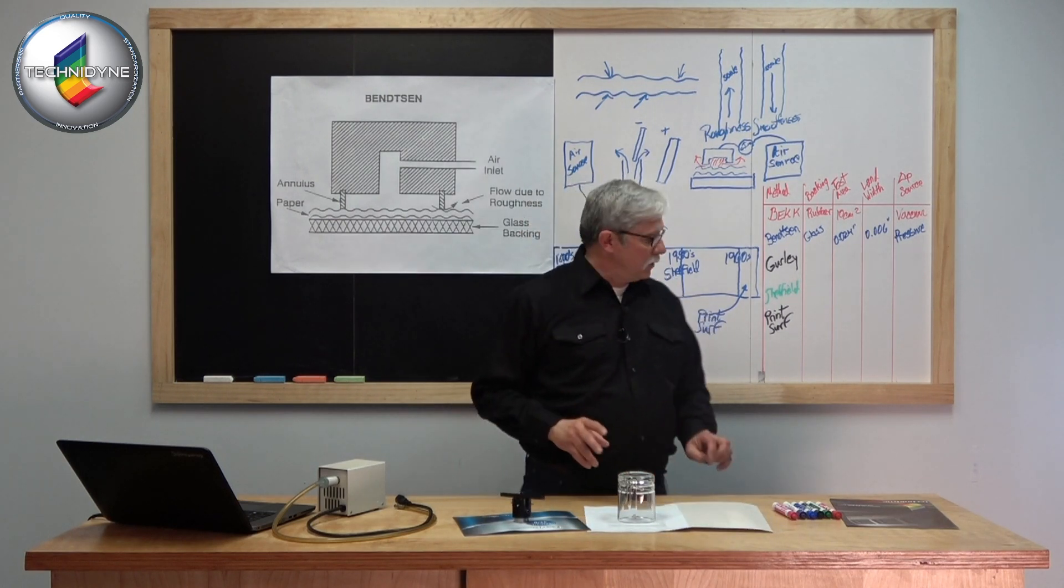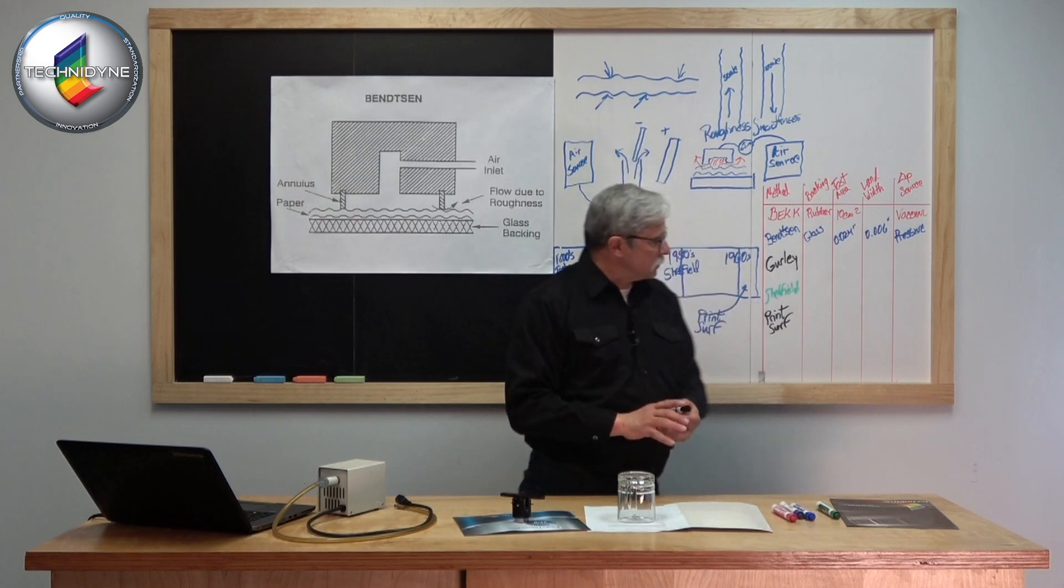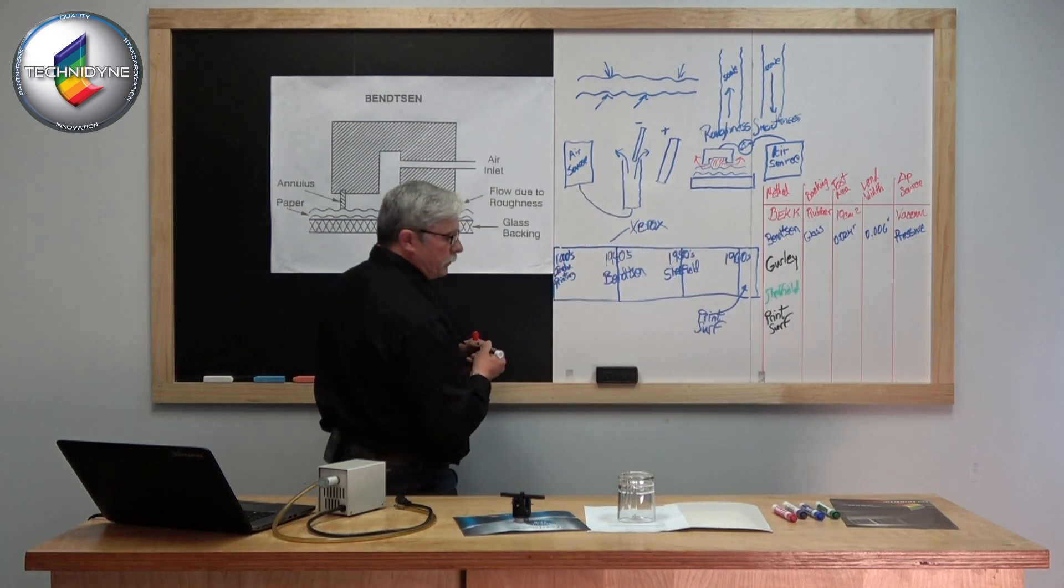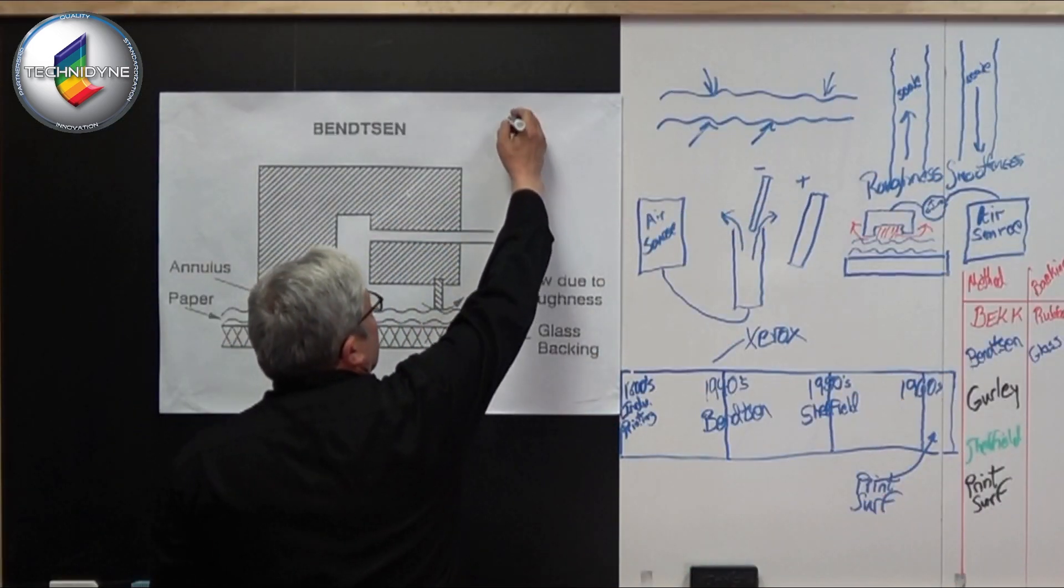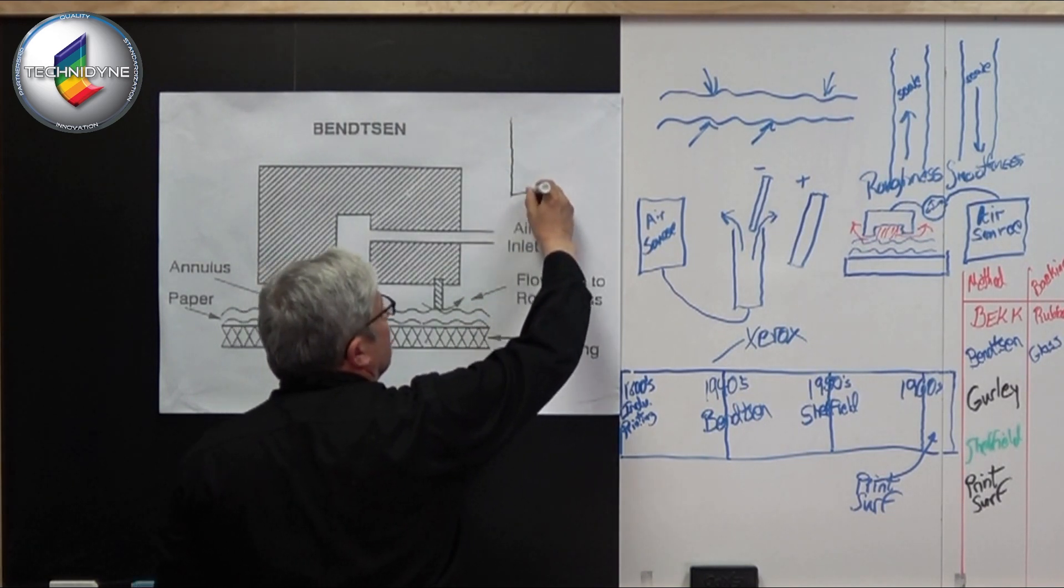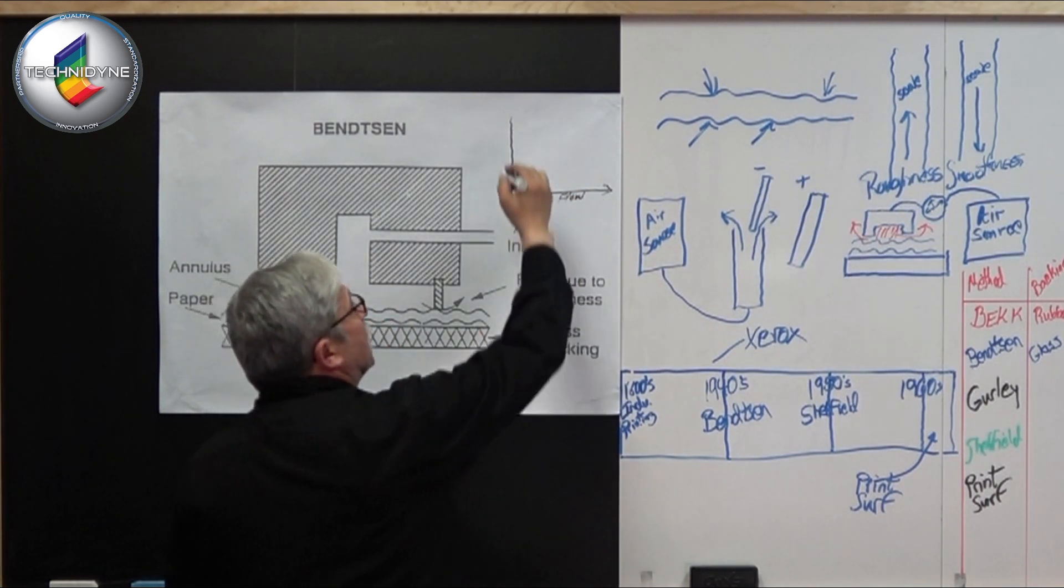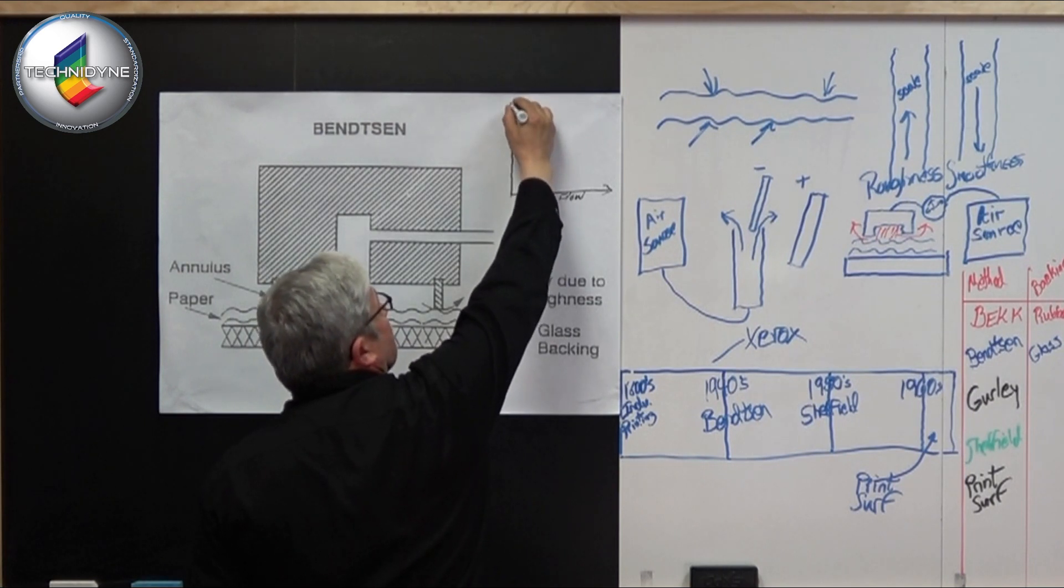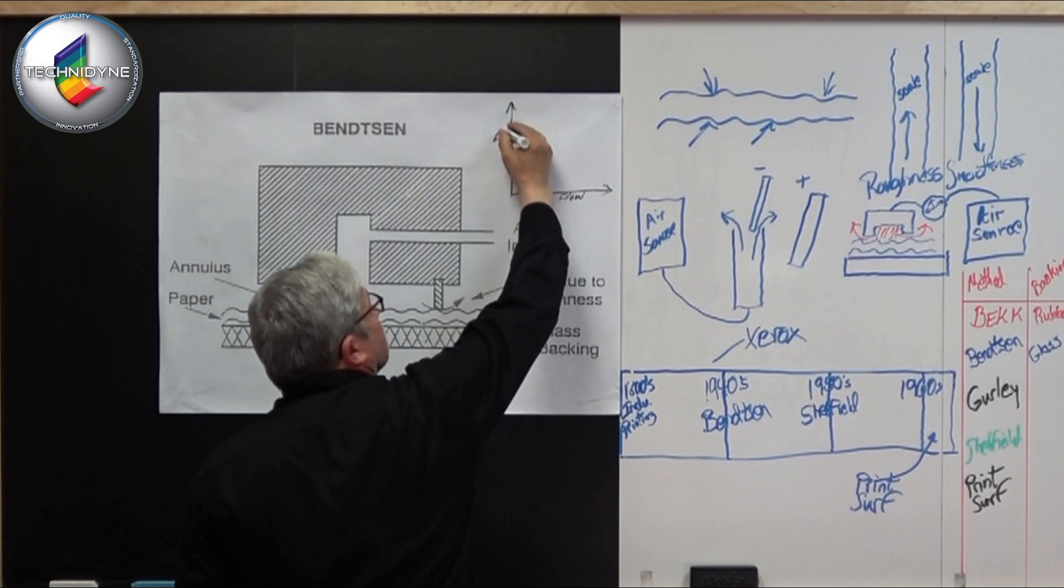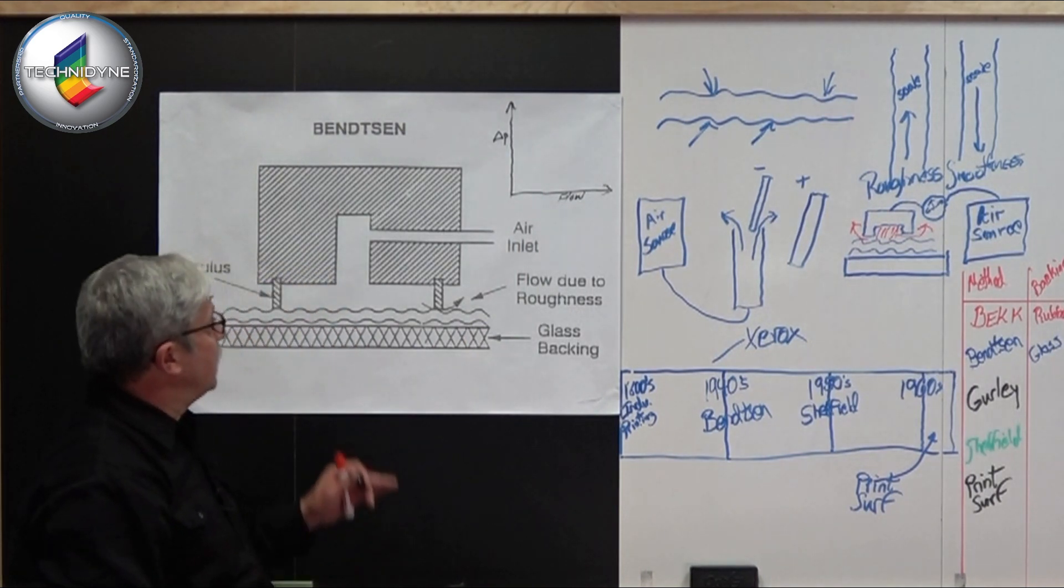Now we've got some significant air movement across here, but our pressure drop starts to degrade as we start to increase the flow. That's simple physics. If I have flow on my x-axis and pressure drop on the y-axis...